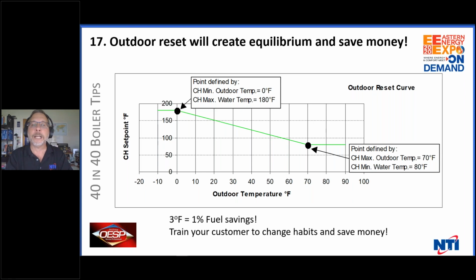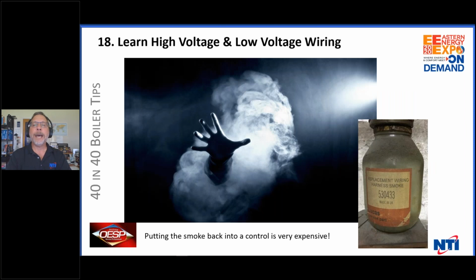Learn it. And for God's sake, stop taking the outdoor sensor off because people were complaining that it was getting too cold. And stop setting them at 180 degrees and letting them run there. Please use the outdoor reset. It will save your boilers. It's less stress. And for God's sake, it will save them money. So please learn it. Learn high and low voltage.